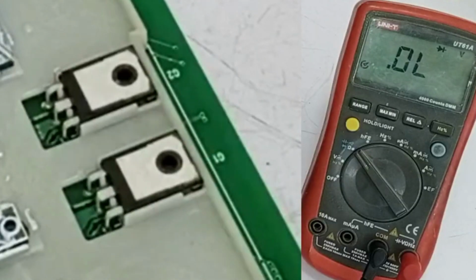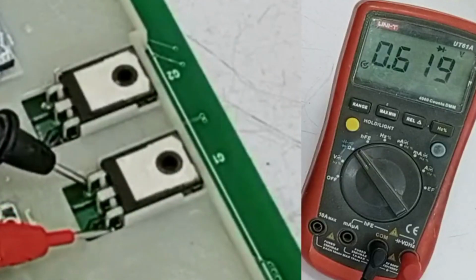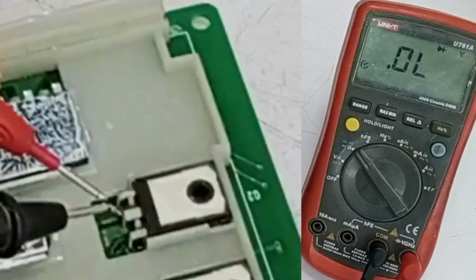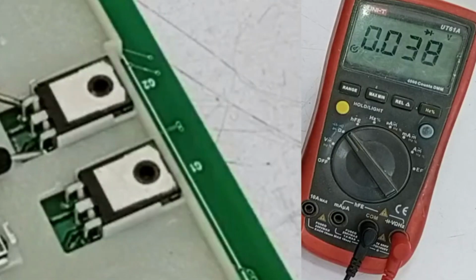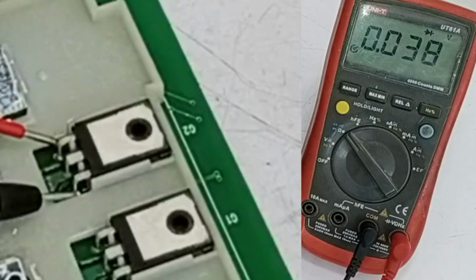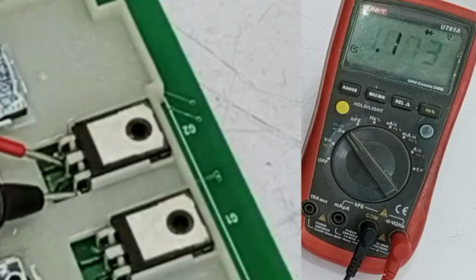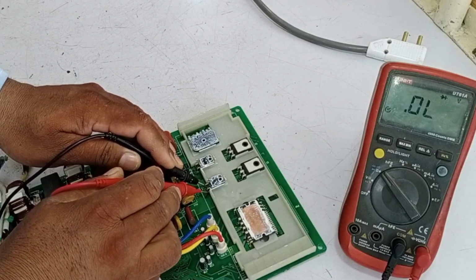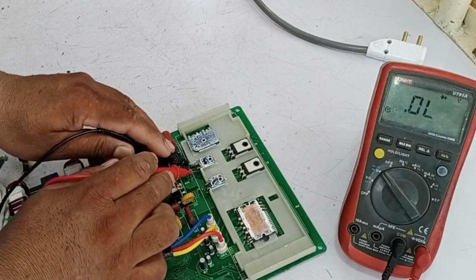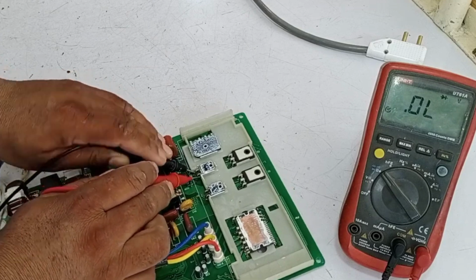Now let's check the IGBTs. I can see that we're getting voltages, and there's no short circuit in any of them. Moving on to the second IGBT. Here we see that one of the IGBTs is completely shorted, and it's causing the IPM to show disturbances. Because of this shorted IGBT, the entire PCB appears dead. On checking the rest of the diodes, they all seem fine, with only this one IGBT shorted.